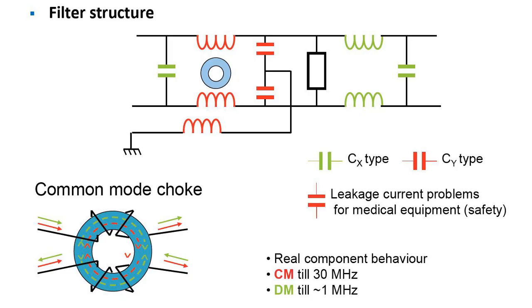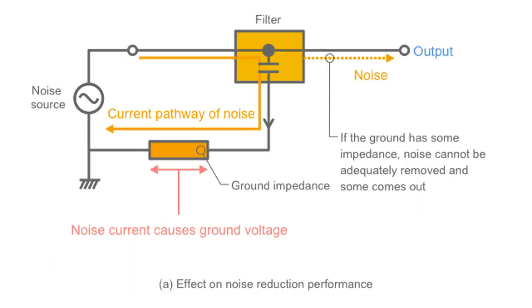Power Line Filter Structure: According to the characteristics of EMI at the power port, the EMI line filter is a passive low-pass filter, which transmits AC to the power supply without attenuation and greatly attenuates the EMI noise incoming with AC.